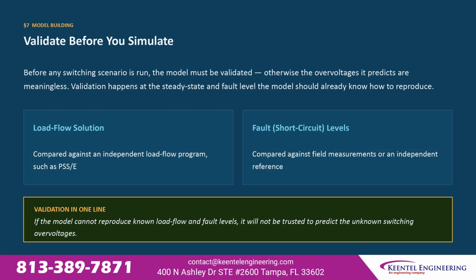Before any switching scenario is run, the model must be validated. If it cannot reproduce conditions it already knows, there is no basis for trusting what it predicts about conditions it does not. Validation happens at two levels. The load flow solution produced by the PSCAD model is compared against an independent program. PSSE is the standard reference.